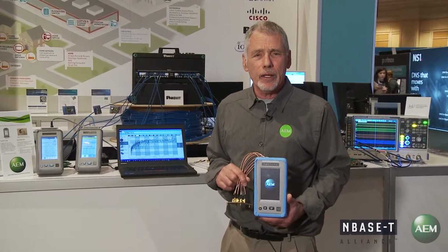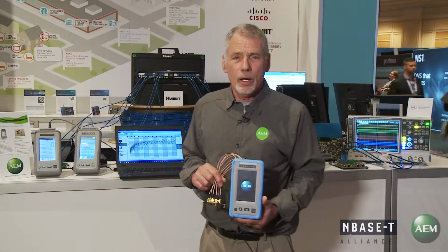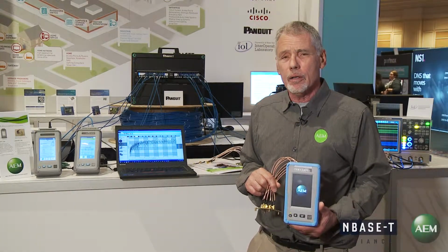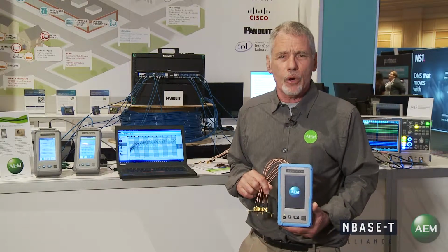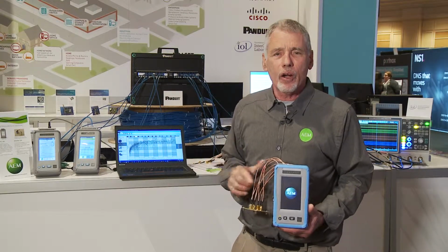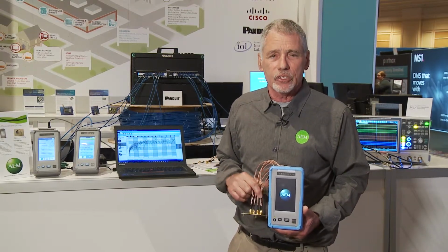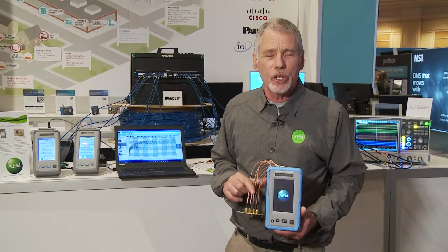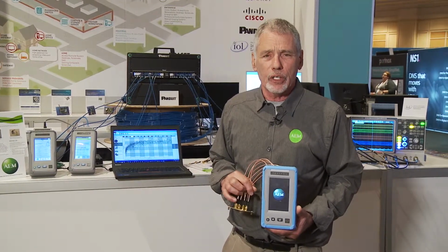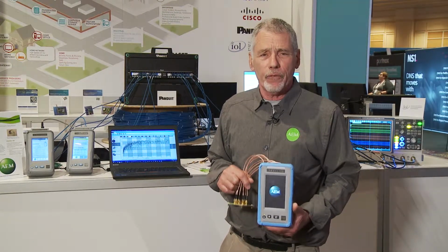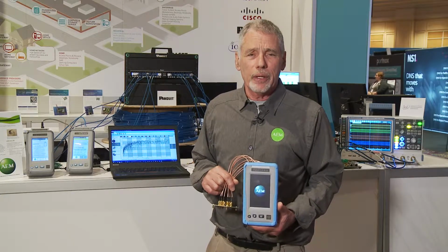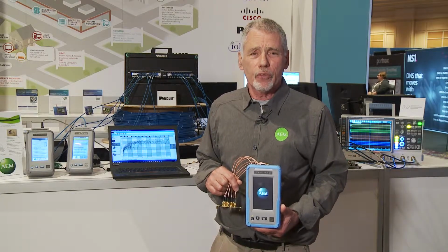In particular today, we have the compelling need to measure at low frequencies with the introduction of data rates down to 10 meg. So we're going from, in some cases, 400 gig to 10 meg, and a lot of these high-end vector network analyzers start off at 1 megahertz. And this enables you to have a solution for a lot of these lower frequencies. It's an optimized and price-effective solution for all vector network analyzer measurements for all of the bandwidths between 100 kilohertz and 3 gigahertz.